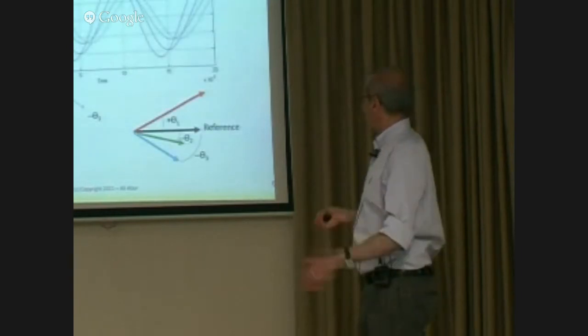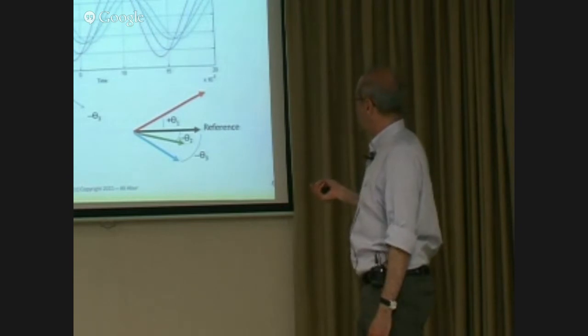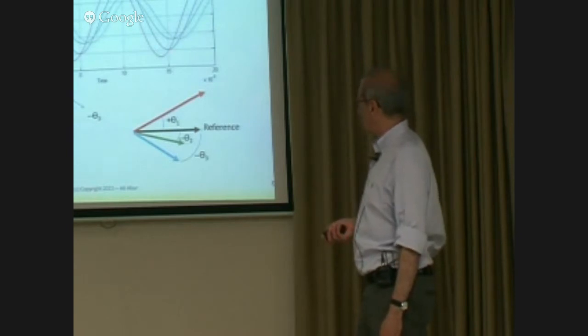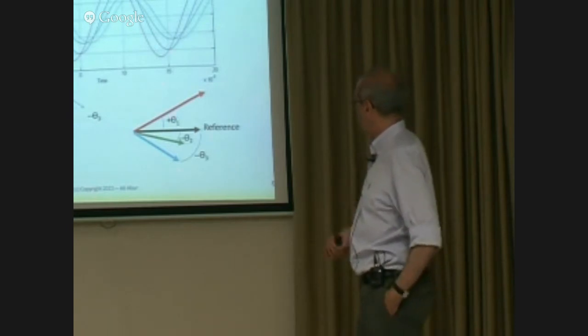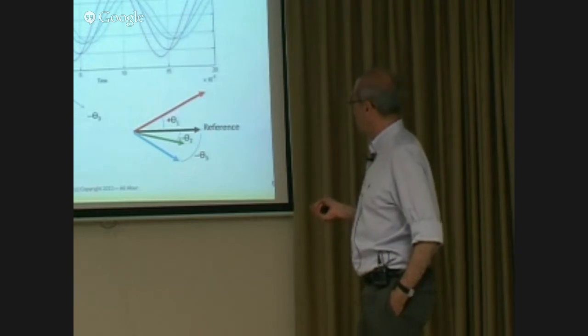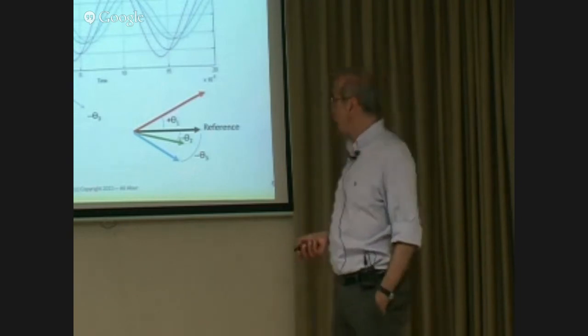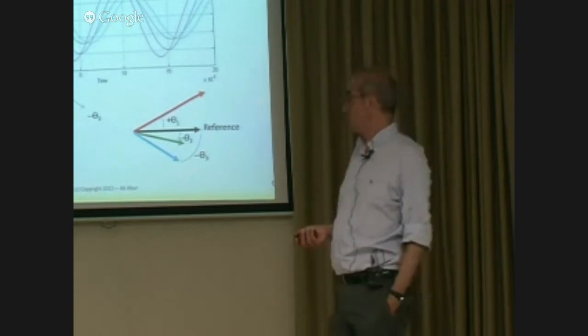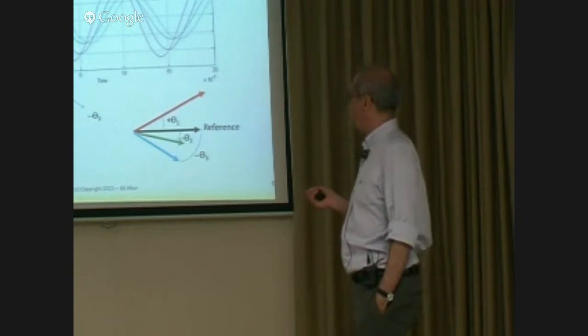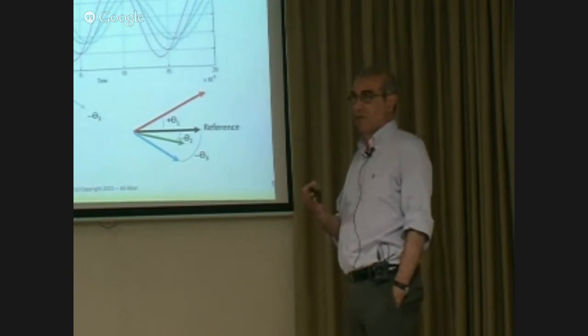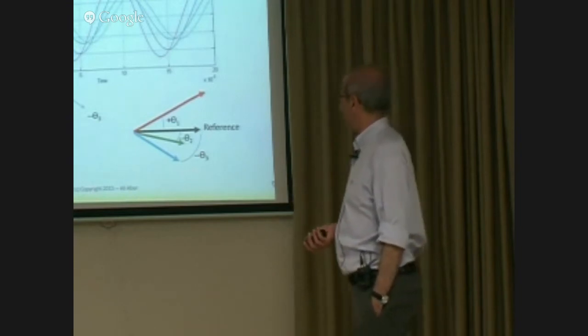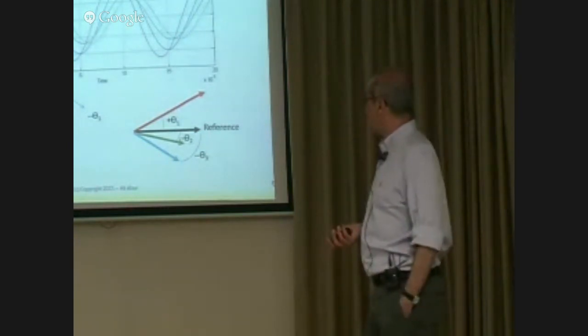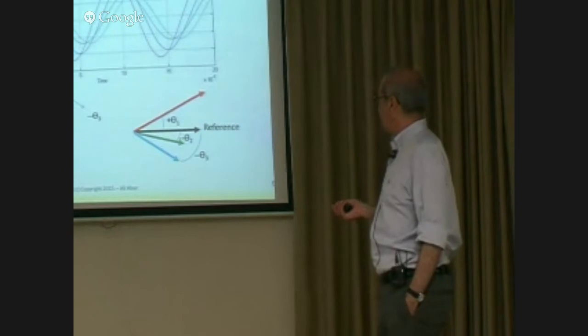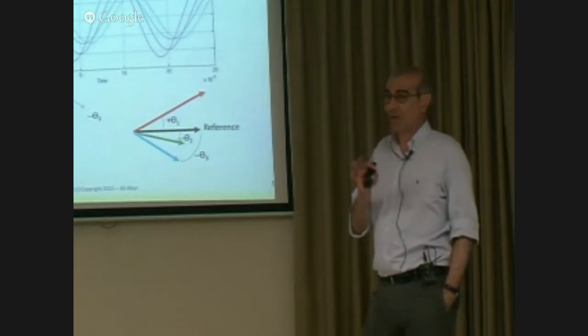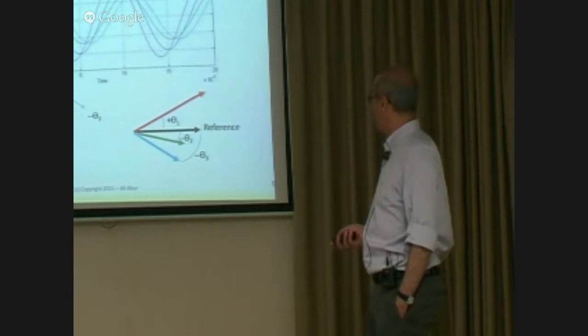So the bottom line is, you collect these samples, and from these samples you create corresponding phasors, which will look something like this. Of course you need a reference for these, and the reference turns out to be the GPS, basically. You don't pick one of these as your reference; you pick the GPS, or whatever timestamp is on that signal, as your reference. So there is really no reference PMU - we do not pick a specific PMU as a reference.